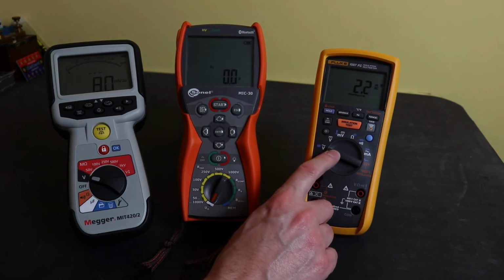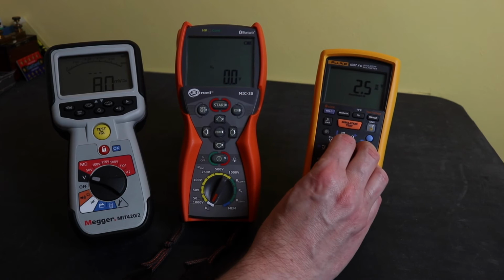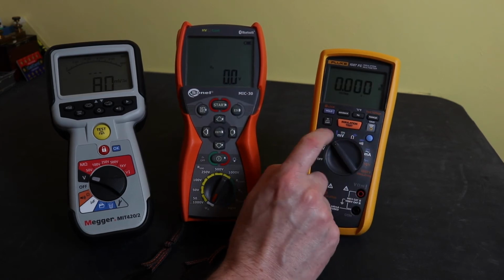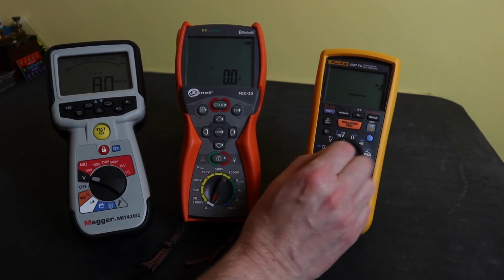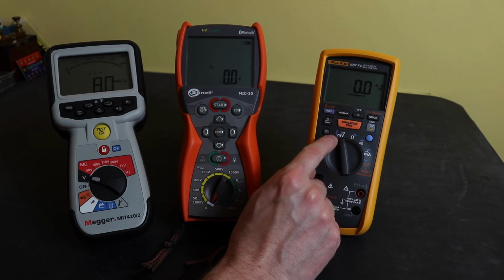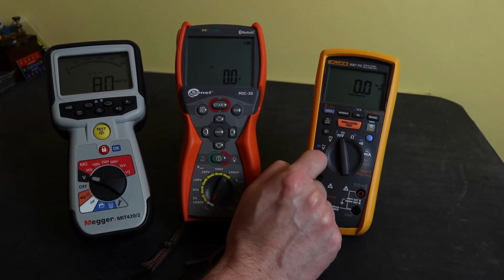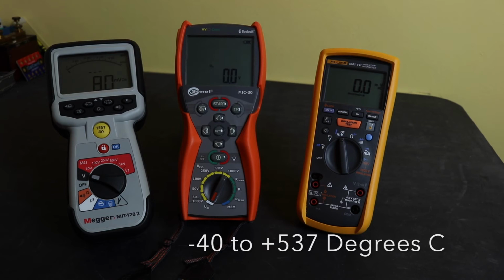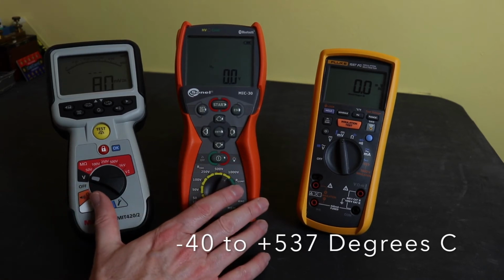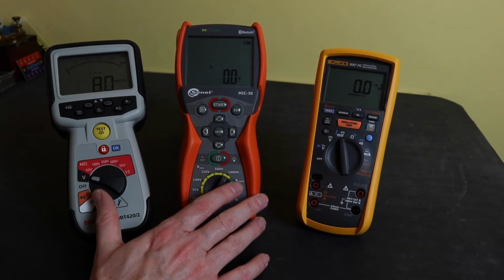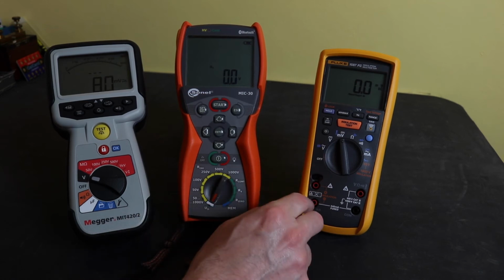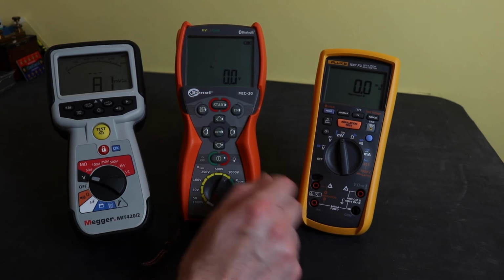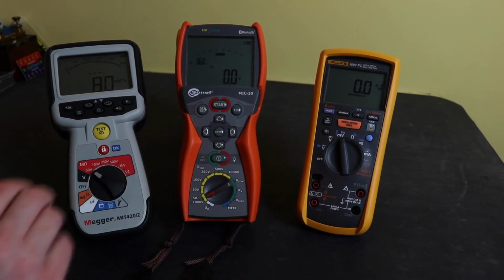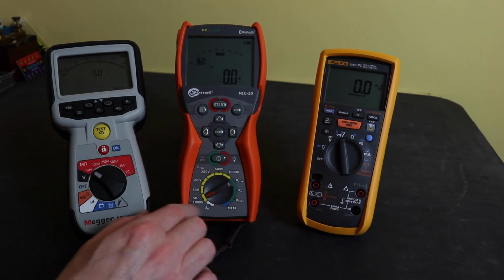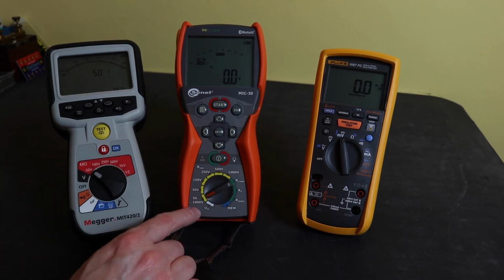To go to DC mode on the Fluke, you have these extra positions, which is DC volts and then millivolts DC, and in the millivolts DC position you also have temperature measurement with the included thermocouple. Neither of these two instruments will measure temperature. Next position round, let's go insulation. Both the Megger and the Sonel move to insulation testing on the next position.